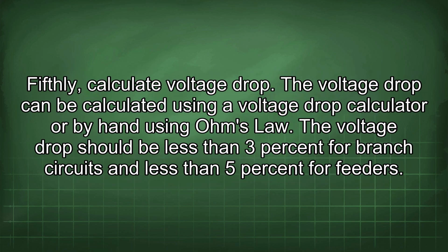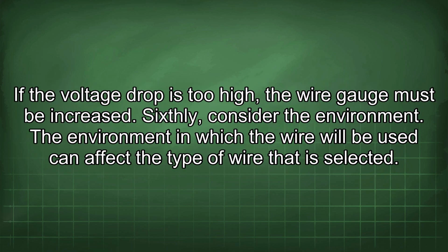Fifthly, calculate voltage drop. The voltage drop can be calculated using a voltage drop calculator or by hand using Ohm's law. The voltage drop should be less than 3% for branch circuits and less than 5% for feeders. If the voltage drop is too high, the wire gauge must be increased.